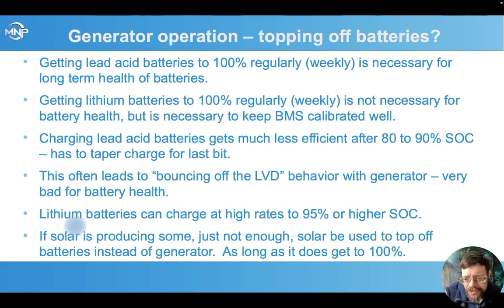It can get out of calibration, and say it gets 1% out of calibration each day that it's cycling and doesn't get up to 100%. That doesn't seem like a lot, but over 2 weeks, that's 14 days. That could be 14% different. And if you think your batteries are at 20% and they're really at 6%, that could be a major problem. So that's why we want to get them up there regularly to keep that battery management system calibrated and have an accurate state of charge that the battery's reporting.